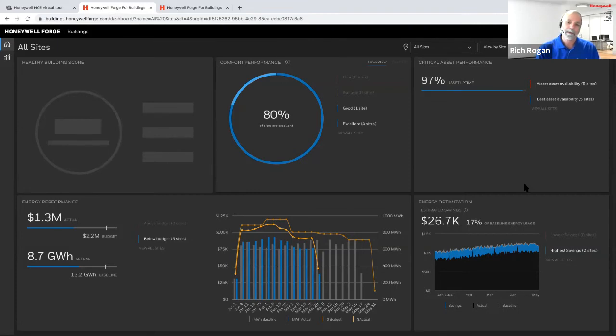We're not controlling from Honeywell Forge. We're writing to set points that already exist in the controls within the building itself. Those set points include chilled water and hot water supply temperatures, differential pressure on the pumping systems, and if it's a variable volume air handling system, the static pressure as well as the supply air temperature.